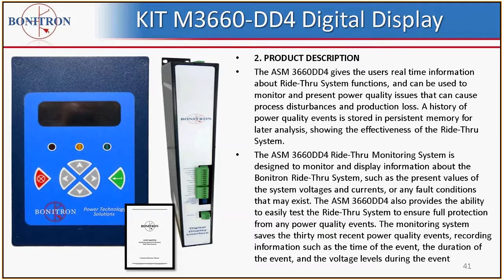So this allows you to see what your utility power is doing wherever this is connected to. The ASM 3660DD4 is designed to monitor and display information about the ride-through system also, such as the present values of the system voltages and currents. So it's not just monitoring the actual ride-through unit, it monitors around the ride-through unit. In other words, DC bus voltages and AC line and things like that. It will save the 30 most recent power quality events, records information such as time of event, duration of the event, and the voltage levels during the event. So it does give you a good picture about what your utility power is doing once it's installed.